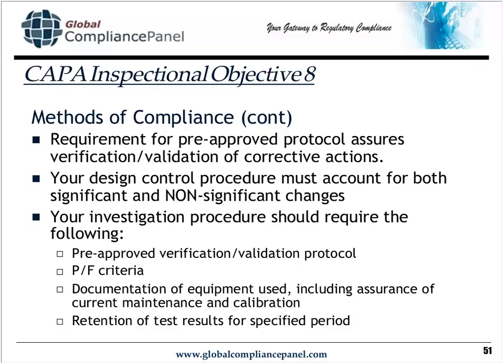Make sure that the equipment used is documented by model and serial number, including expressly writing down on the test report the calibration due date of the product. Not the most recent calibration date, because that doesn't tell you when the calibration is due. It tells you when the calibration was performed, and that's insufficient. And make sure that your procedure talks about how often, and for what period of time, you retain your test results.